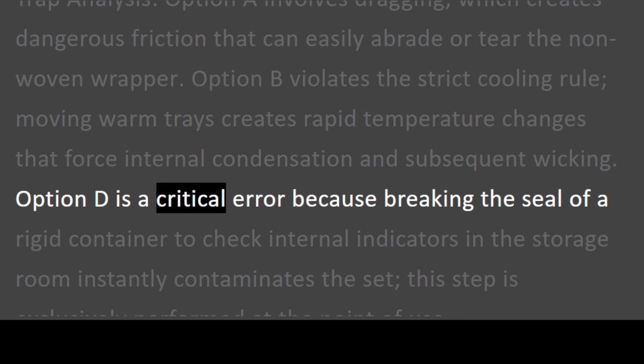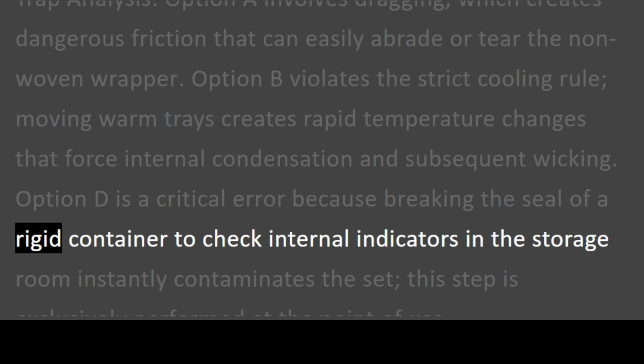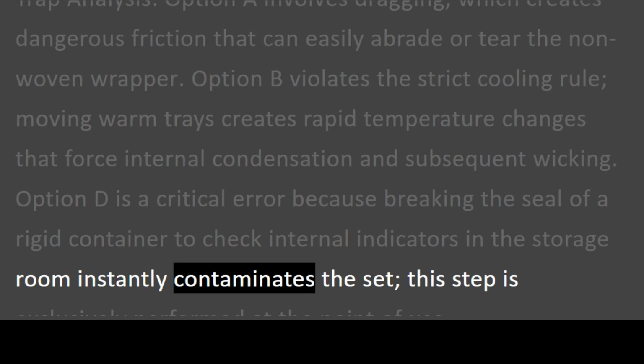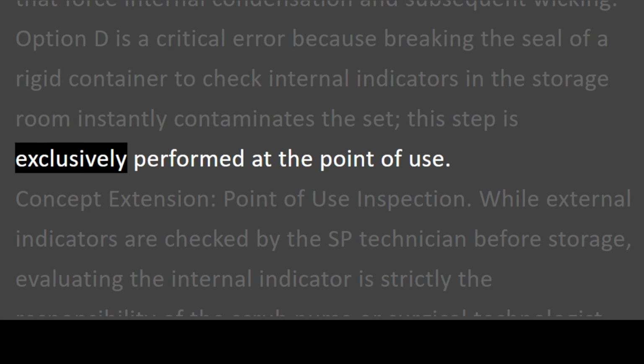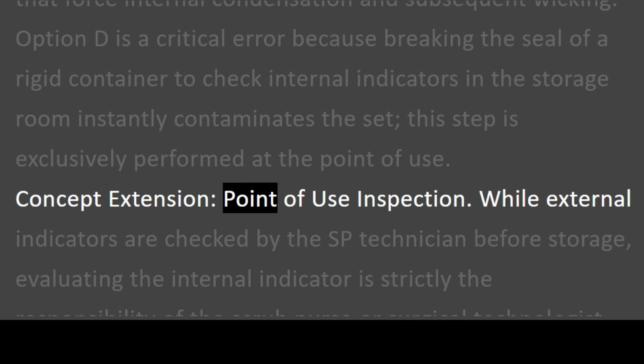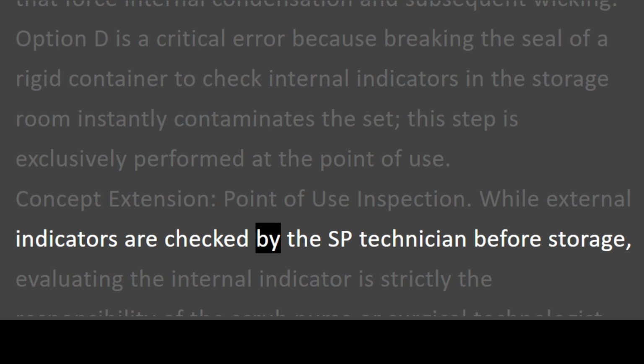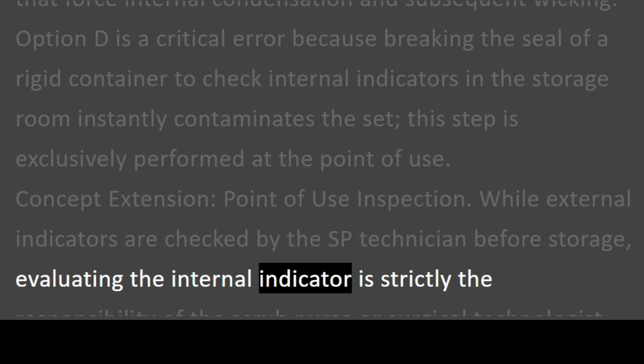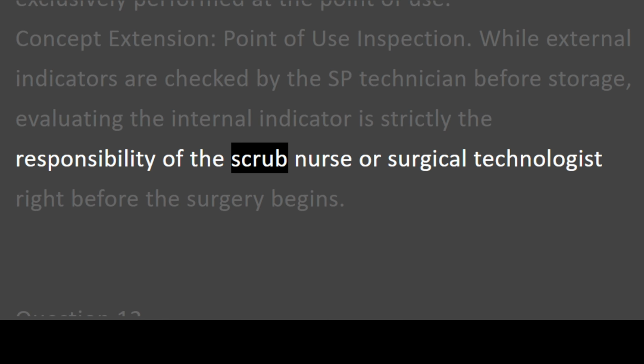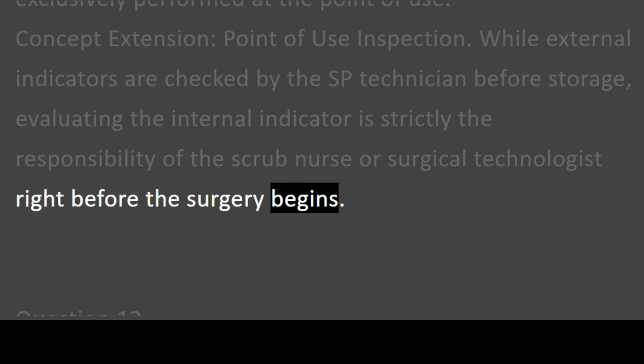Option D is a critical error because breaking the seal of a rigid container to check internal indicators in the storage room instantly contaminates the set. This step is exclusively performed at the point of use. Concept extension, point of use inspection. While external indicators are checked by the SP technician before storage, evaluating the internal indicator is strictly the responsibility of the scrub nurse or surgical technologist right before the surgery begins.